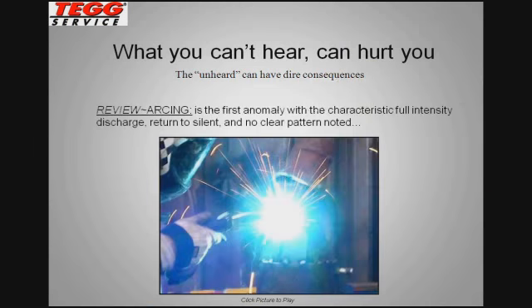Just reviewing the definition of some of these things we're looking for. Arcing is the first one we talk about. If you wanted to describe what arcing is, you have a full intensity discharge that erupts, and then it goes to full silent. And there's not a clearly defined pattern with respect to time when this may occur. It depends on how severe the situation may be. You can associate that with an arc welder. When you strike an arc, that's arcing in its purest form. But we have these same types of situations occurring inside electrical equipment at frequencies that you may or may not hear. And when you do identify arcing in its purest form, as you may have been told in the past, failure is occurring right before your very eyes.